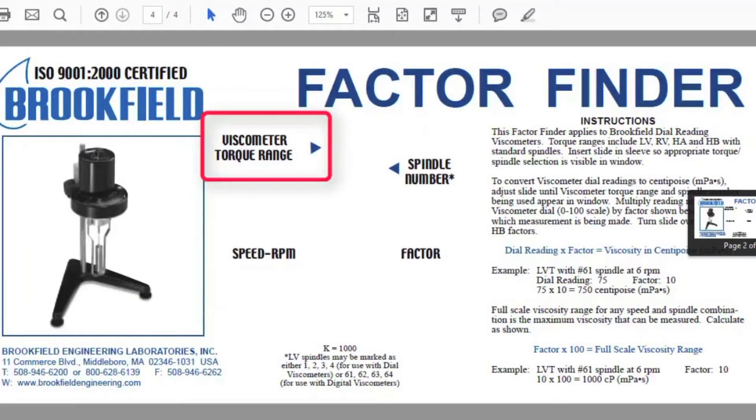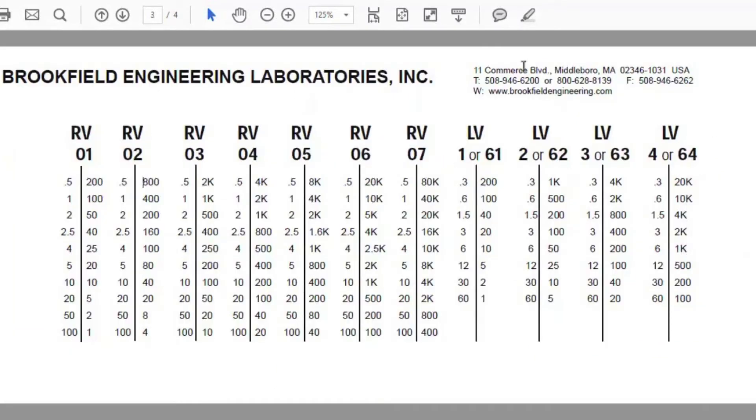To select the appropriate chart, we will have to look at the viscometer torque range and the spindle number. Because an RVDV-E viscometer was used, the conversion charts titled RV will be chosen.